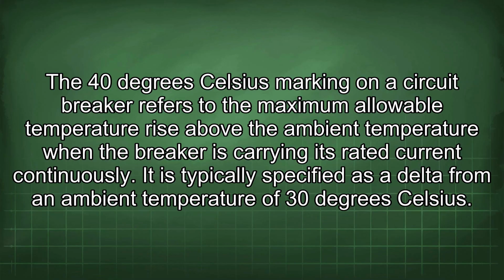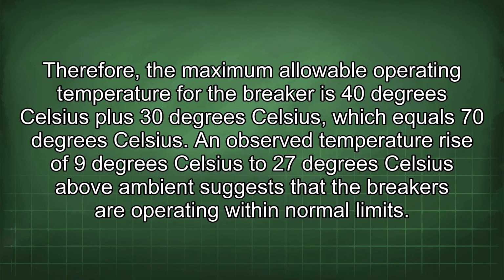The 40 degrees Celsius marking on a circuit breaker refers to the maximum allowable temperature rise above the ambient temperature when the breaker is carrying its rated current continuously. It is typically specified as a delta from an ambient temperature of 30 degrees Celsius.